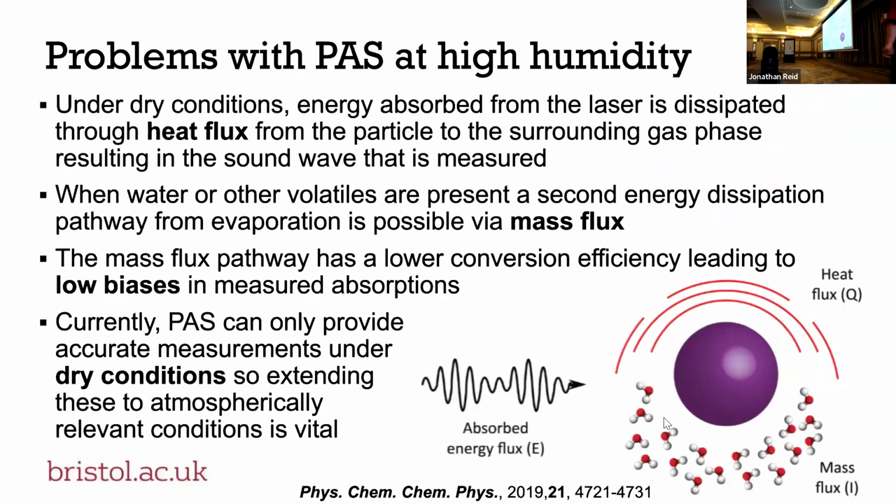So one of the problems with photoacoustic spectroscopy is that at the moment it only provides accurate measurements for dry particles that haven't got any water or any volatile organics present. And that's because usually the energy absorbed from the laser by the particle is dissipated through heat flux to the surrounding gas phase, which then results in our sound wave that we measure.